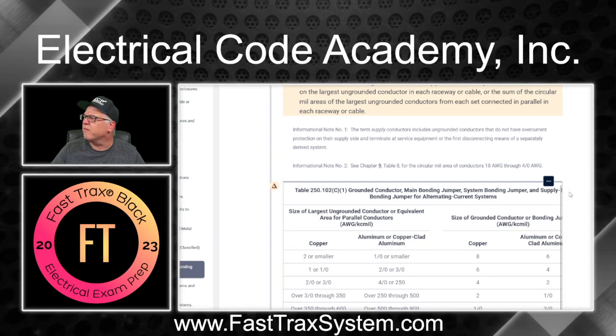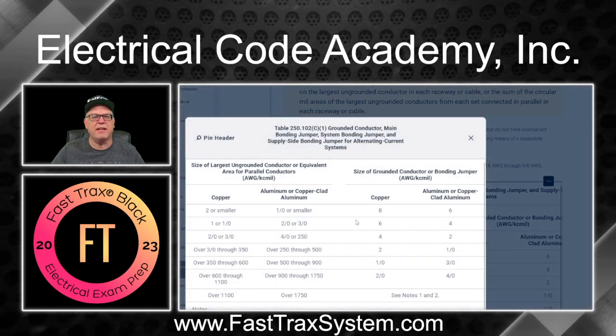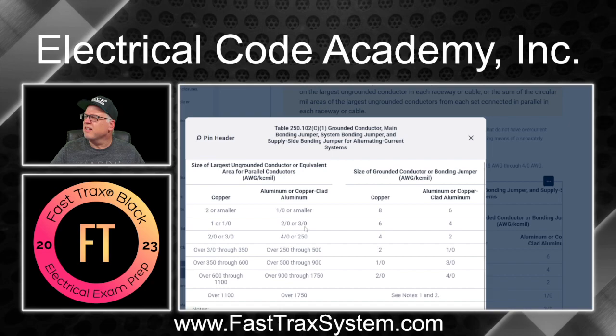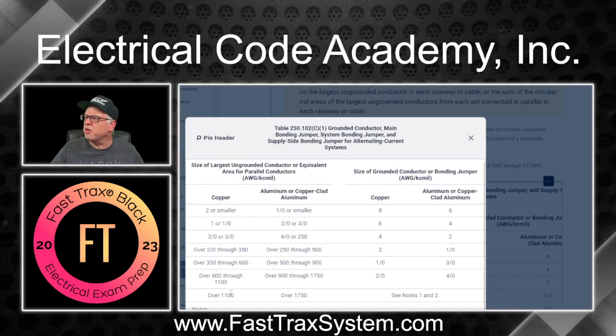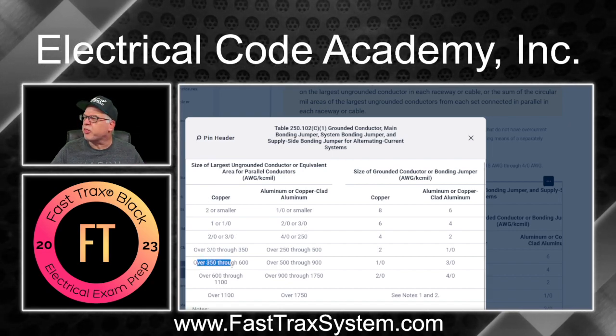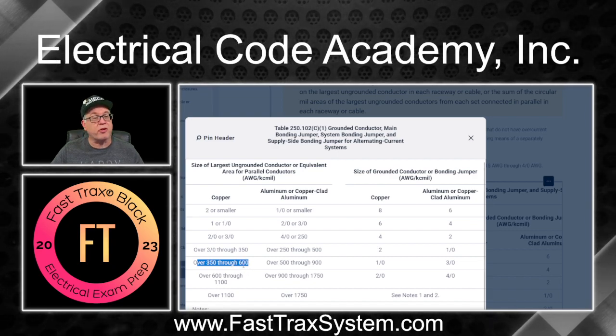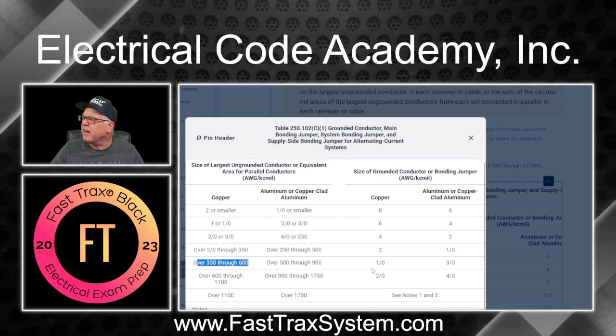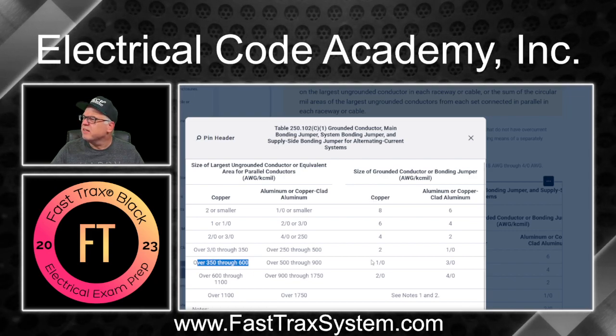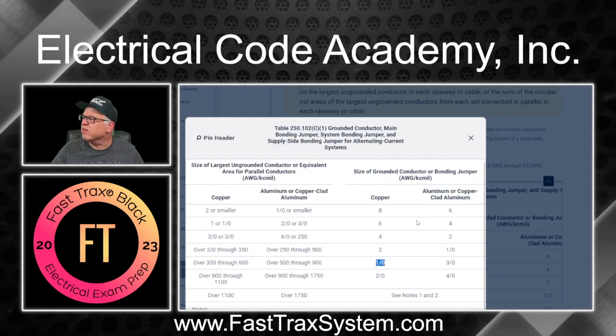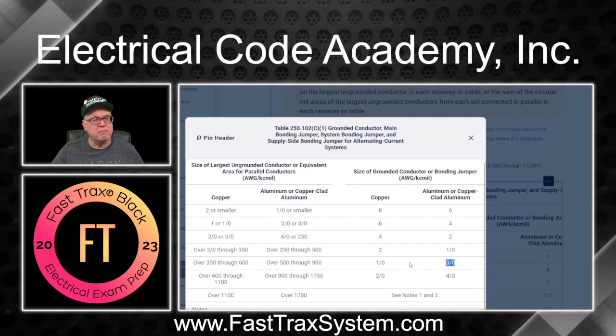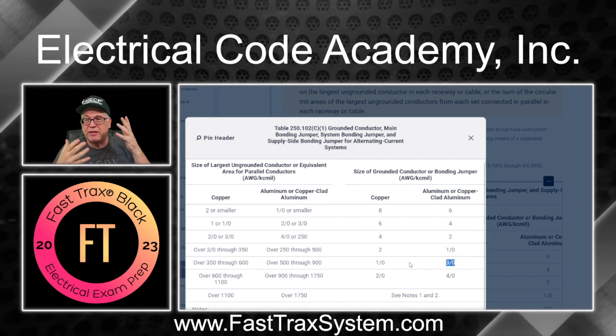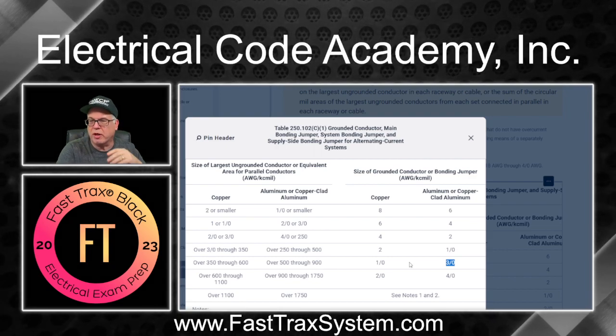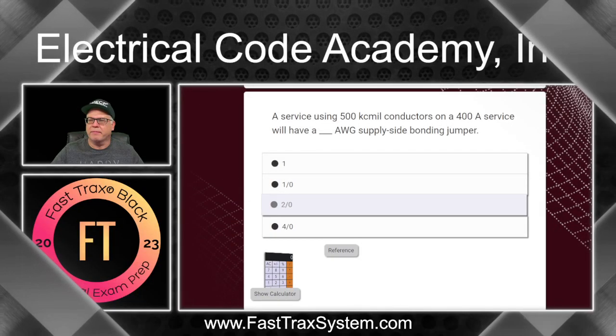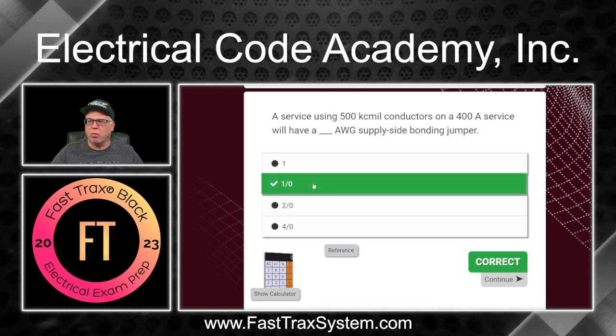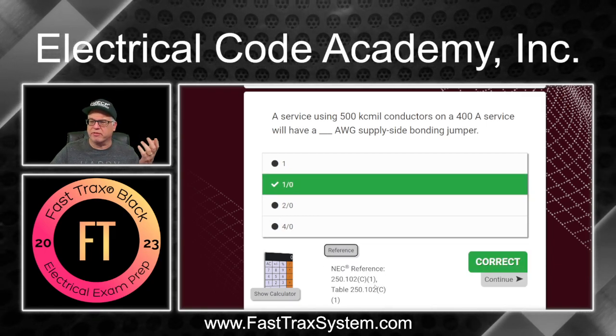All right, so here's the table. Let's click on it, expand it. This is what y'all are familiar with seeing. Over here, it's a 500 kcmil, so it falls between over 350 through 600. Again, that's 600 kcmil, okay? And then over here, if it's copper, then it's a 1-aught. If it was aluminum, it'd be a 3-aught, okay? Now, remember, copper unless stated otherwise, right? So we're going to come back to our question, and it clearly is 1-aught, and here's your reference.